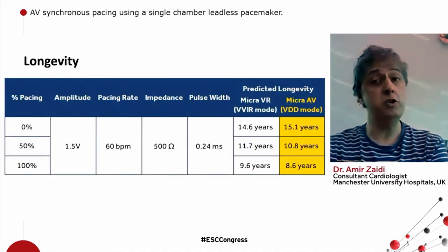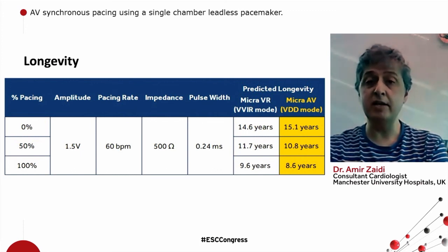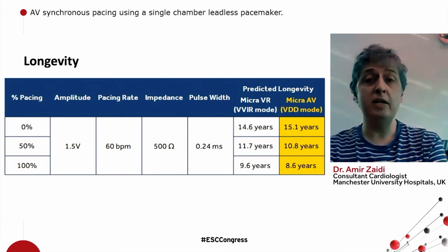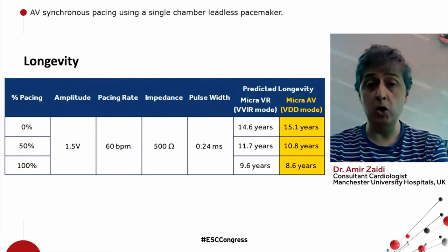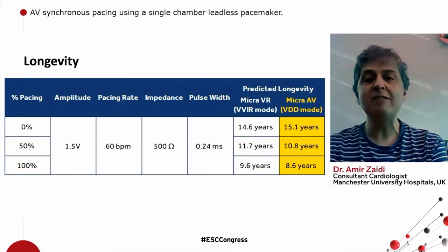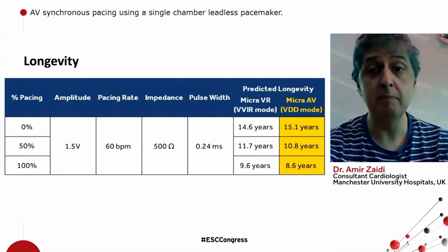Longevity is very good. Predicted longevity, obviously, at this stage, but depending on the amount of pacing, we would expect between 8 and 15 years in VDD mode. So the predicted longevity is very similar to what we already achieved with Micra VR.